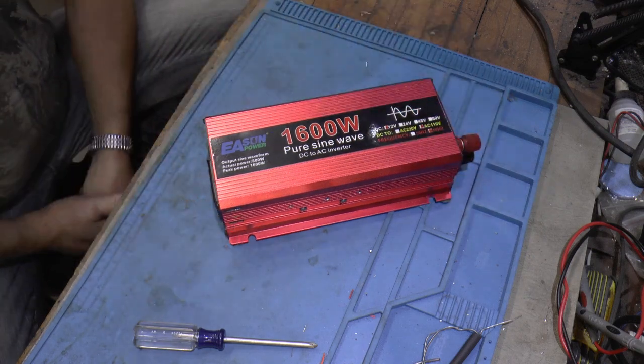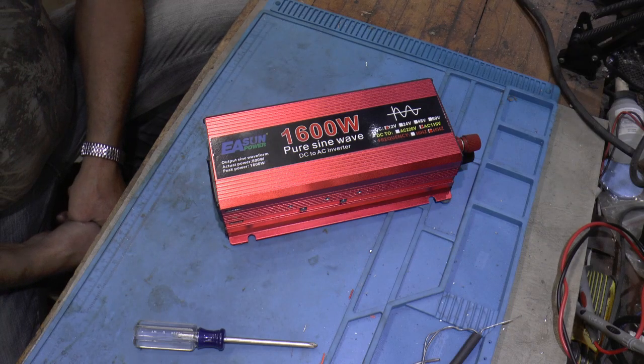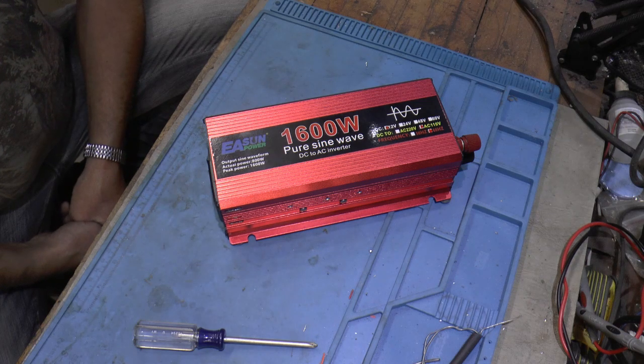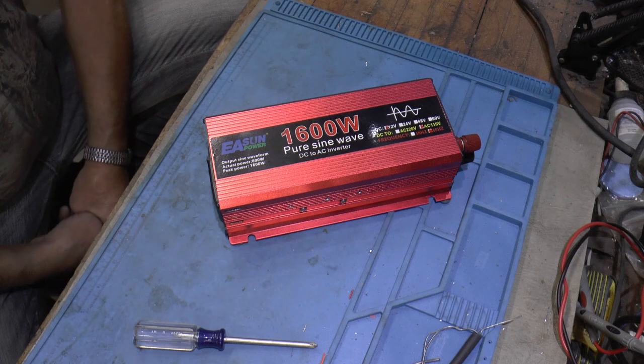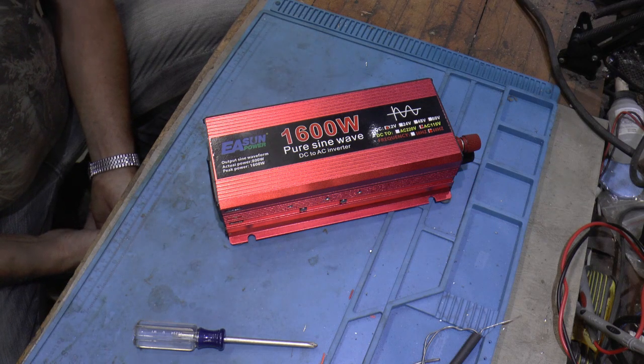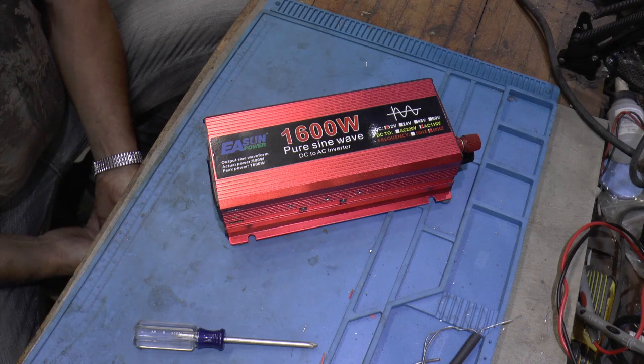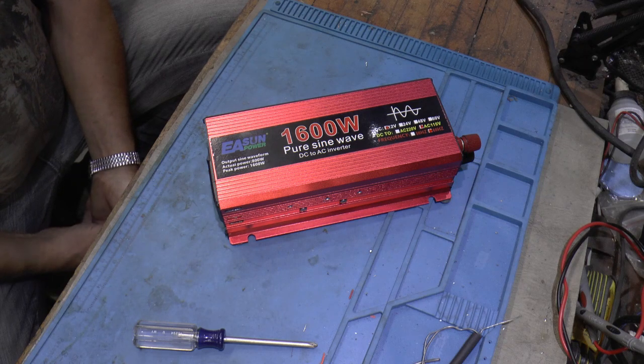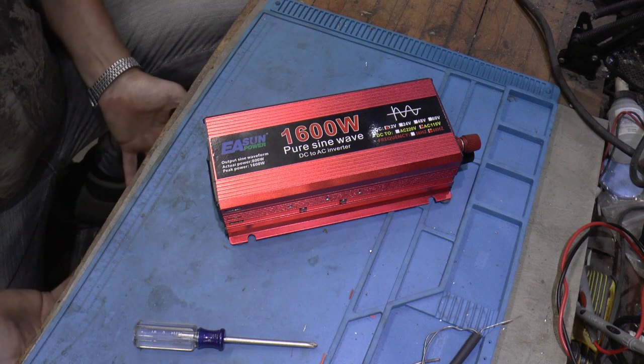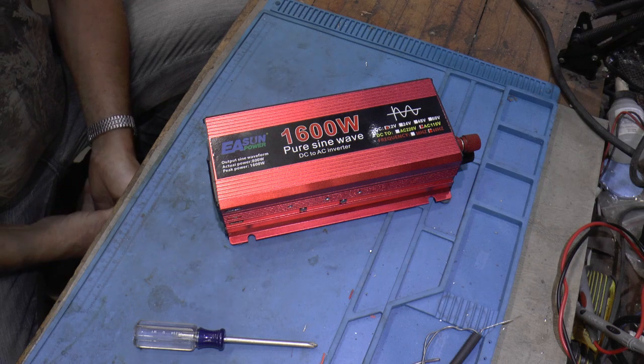I tacked on another 100 watts — just threw a 100-watt incandescent bulb on it — and it would shut down. It didn't do that before when I ran the heaters on it. And I couldn't come up with anything that would cause that. But if I had the 100-watt light on already and turned my 300 watts worth of shop lights on, it didn't bother any. It seemed to only do it when I added that 100 watts on top of the existing load.